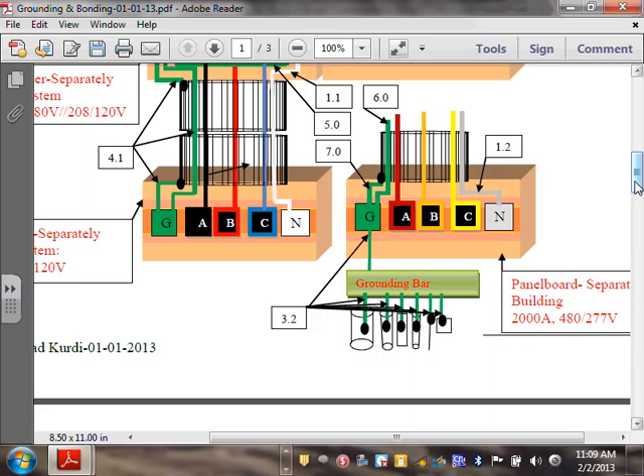Yes, sir. Bond the neutral and ground separately. In the old days, to save copper on the farms, they used to bond the neutral. And now there's an exception in the code for existing buildings where there is no metallic connection between the two buildings. Only existing, no metallic connection, not even a coaxial shield of a cable, because that could be carrying neutral current. You can get away with 4 conductors instead of a 5 conductor cable here. But that's an exception to the rule, not the rule. You're absolutely right. Then you can bond the two together.